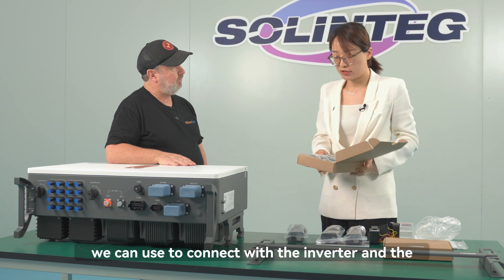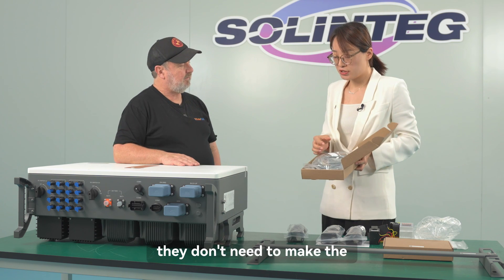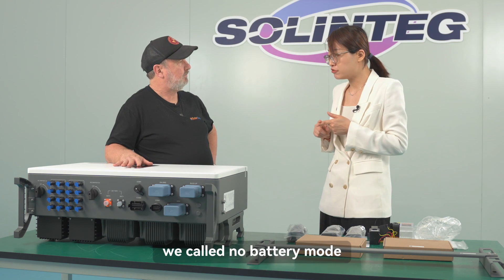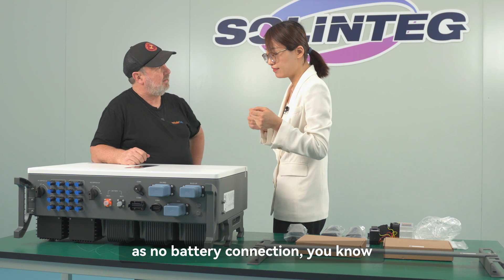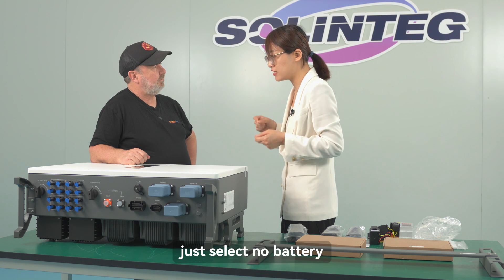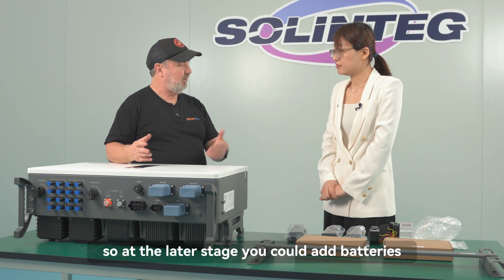This box contains pre-wired cables to connect the inverter and battery — a CAN cable and a BMS cable. If you have a battery, you connect these cables; you don't need to make the cables yourself. If you don't have a battery, you can still use this unit. Our inverter has a 'no battery mode' — you select 'no battery connection' on the display. It can operate as a pure grid-connected inverter, battery-ready to add batteries later.